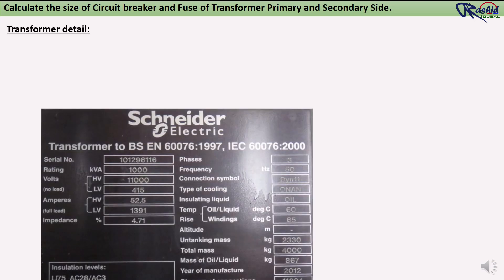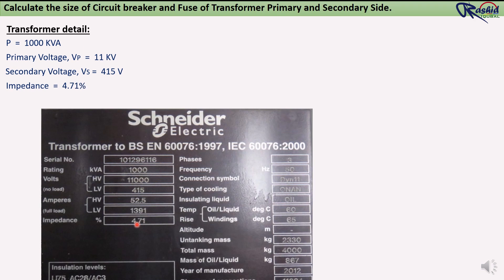Example 1: Calculate the size of circuit breaker and fuse for the transformer primary and secondary side. From the transformer nameplate, we can collect all information: transformer size is 1000 kVA, primary rating is 11 kV, secondary rating is 415 V, impedance is 4.71%, and transformer connection is delta-star type.